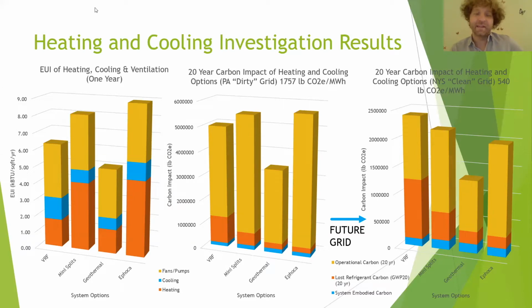But you can see that the relative carbon impact changes as the grid gets cleaner, because different things become more or less of the carbon pie. VRF looks pretty good when you have a dirty grid because your operational carbon is the biggest piece of the pie. But as the grid gets cleaner, or you add solar and batteries to your building, the refrigerant becomes more of an impact. So when you have a clean grid, VRF starts looking pretty bad for carbon because of all the refrigerant leaking into the environment.